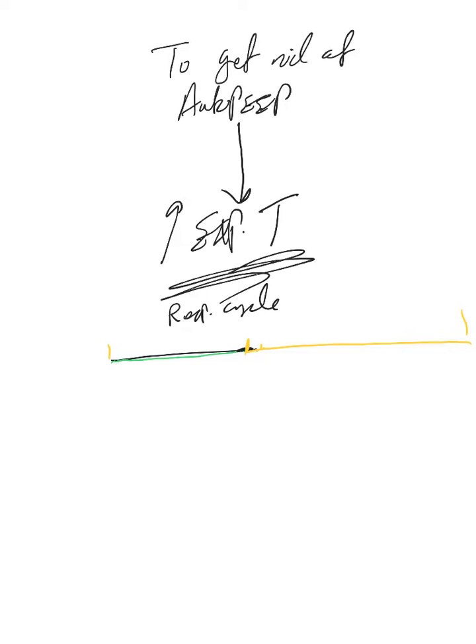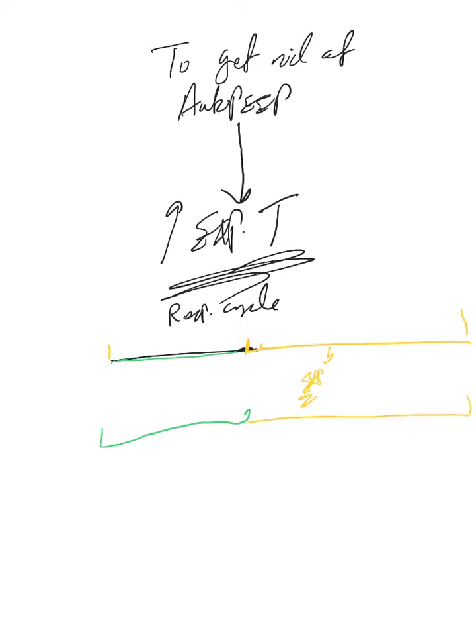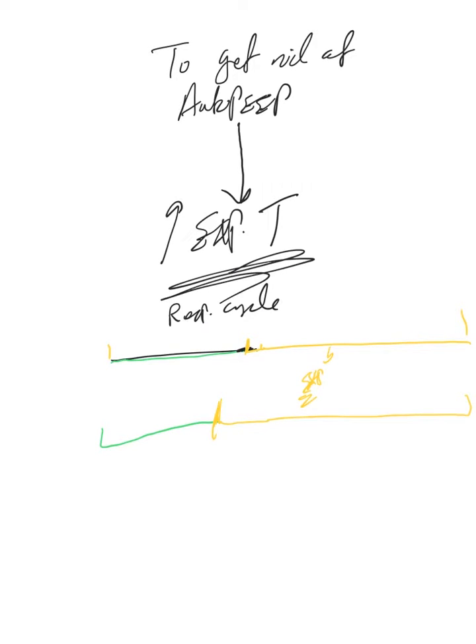The other way is doing like this: keep the green as it is and increase the whole respiratory cycle. So let me put it this way: increase respiratory cycle and keep the inspiratory time fixed. That will allow the expiratory time to increase.